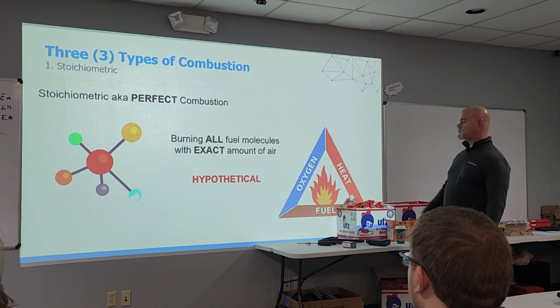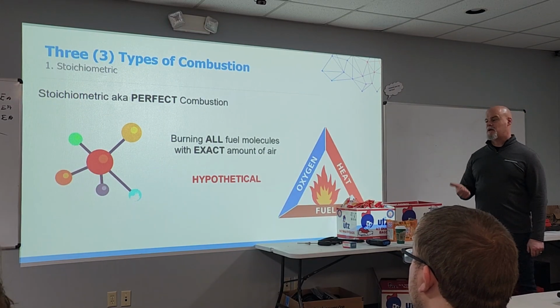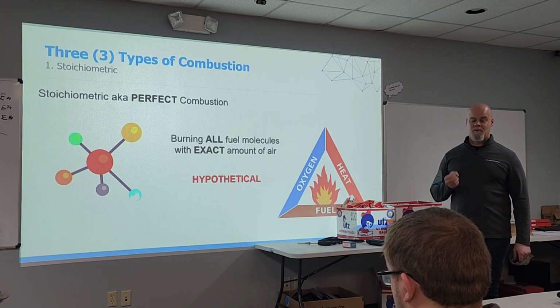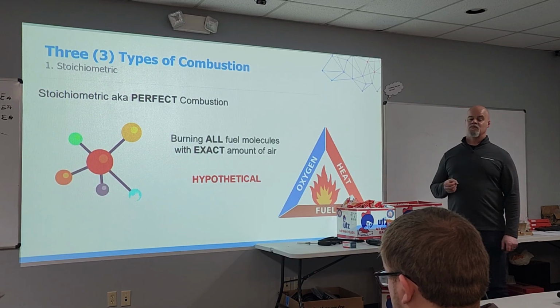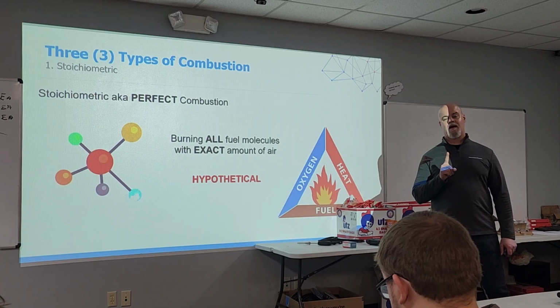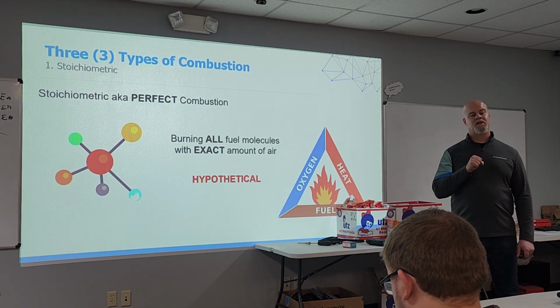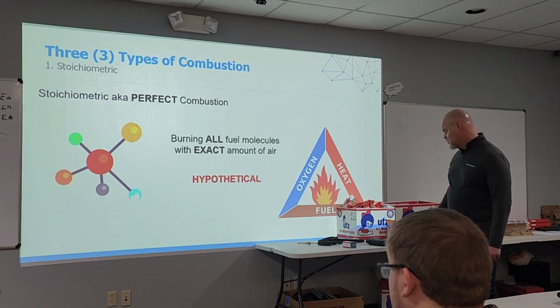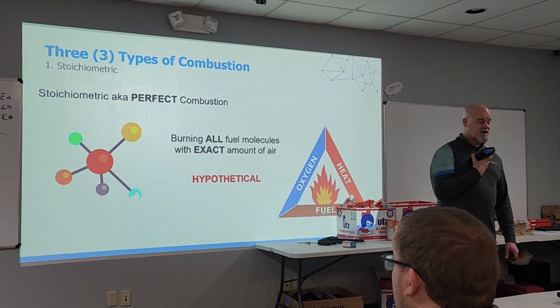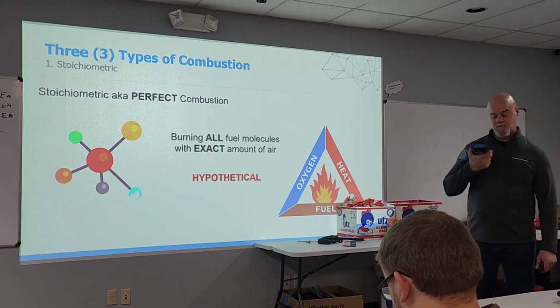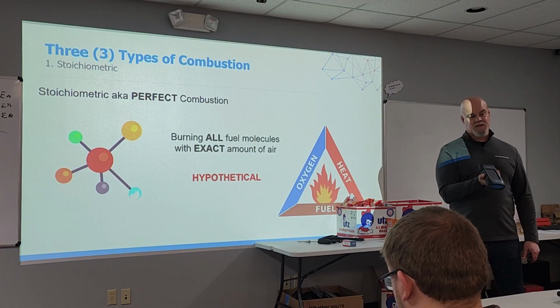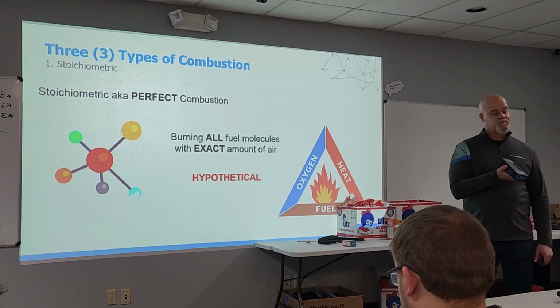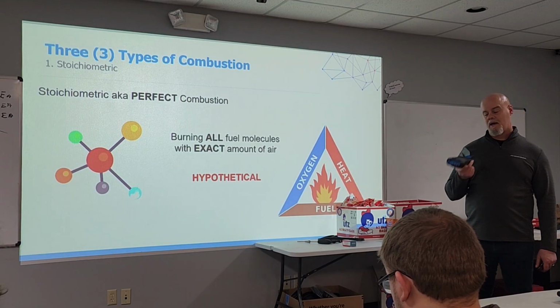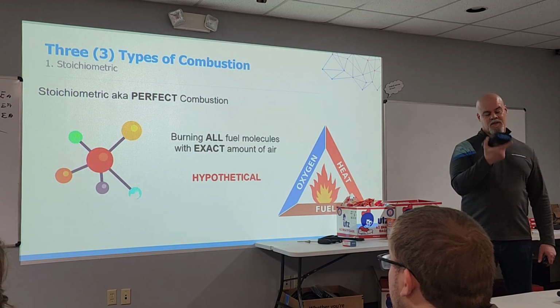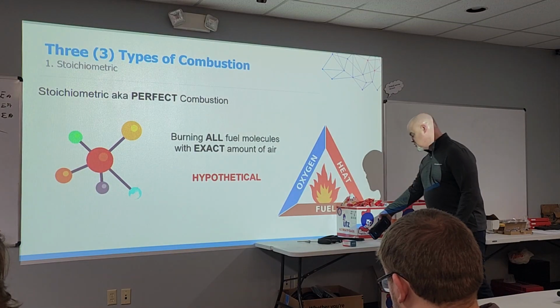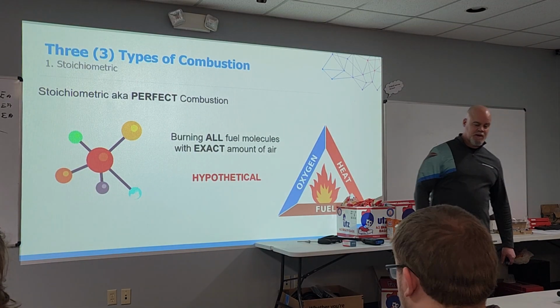So there are three types of combustion. The first is stoichiometric, which we know as perfect combustion. It does not exist, for two reasons. One, it assumes we have 100% oxygen in the air that we breathe, and we do not. If you turn one of these on outside in fresh air with no probes or hoses attached, you'll see 20.9% oxygen. So we're already at a disadvantage - the other 78% is nitrogen, and the other 1% is argon gas.